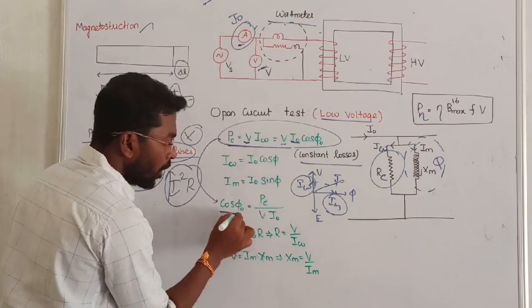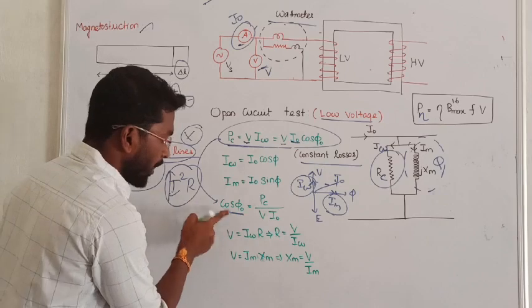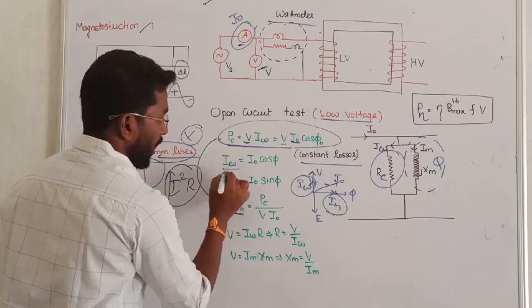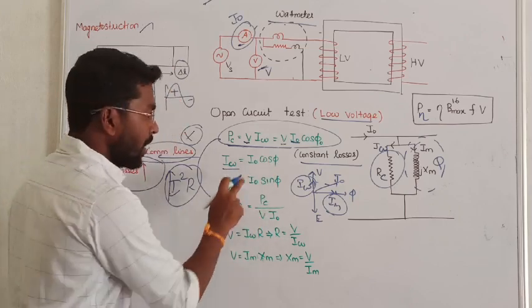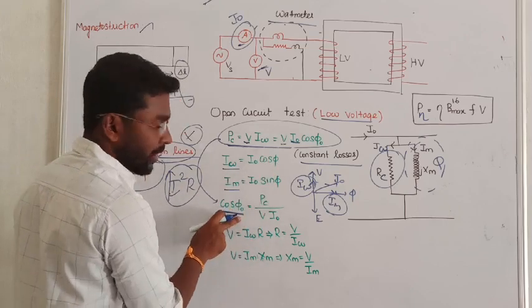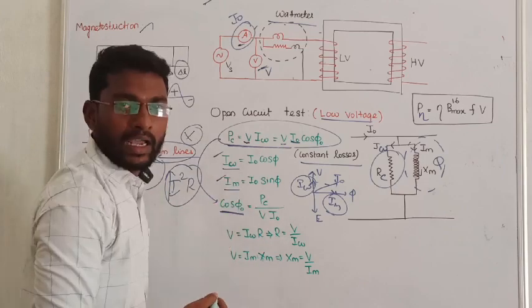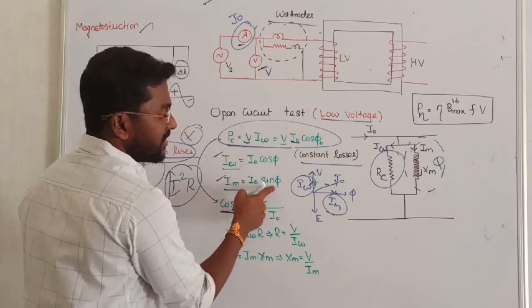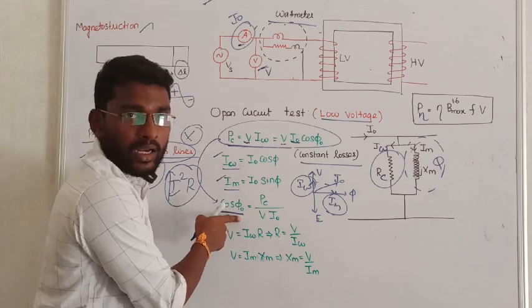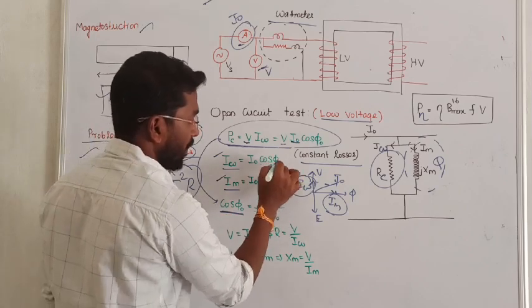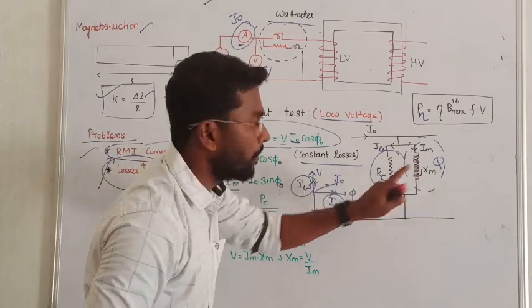From these readings we can find the no-load power factor: cos-phi equals Pc divided by (V times I0). Then we can find Iw equals I0 times cos-phi, and we can also calculate the magnetizing current Im equals I0 times sin-phi. From cos-phi and I0 we can find the value of phi, and from that we determine the core loss current and magnetizing current.